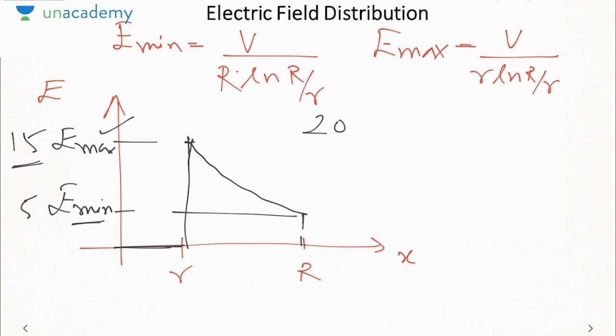Let us say 20. So here the difference is only 5, which means I am utilizing the dielectric very well. But here the difference between the dielectric strength and the electric field is 15. So the dielectric is not getting sufficiently utilized, its strength is getting wasted. You can bear up to 20 kilovolt per mm, but you only have 5 kilovolt per mm electric field. So we choose the dielectric based on Emax, but the desirable condition is that the electric field should be uniform instead of varying hyperbolically. So that is the electric field distribution.